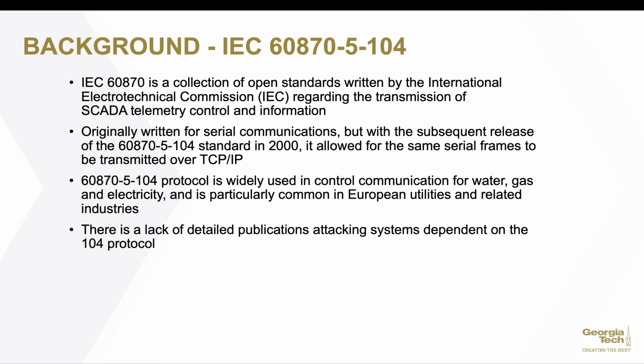The first concept is IEC 60870-5-104. IEC 60870 is a collection of open standards written by the IEC regarding the transmission of SCADA telemetry control and information. This was originally written for serial communications, but with the subsequent release of the 60870-5-104 standard in 2000, it allowed for the same serial frames to be transmitted over TCP/IP.